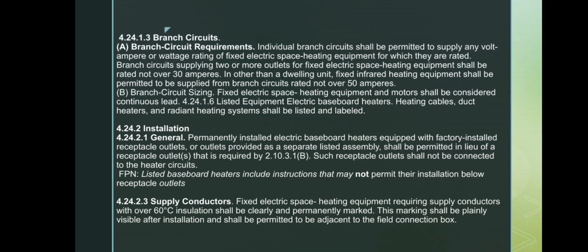The next slide explains the rules of branch circuit and installation for fixed electric space heating equipment. First, under section 4.24.1.3, branch circuit requirements. An individual branch circuit may supply any wattage or volt-ampere rating of fixed electric heaters as long as the circuit is properly rated. If one branch circuit feeds two or more heating outlets, it must not exceed 30 amperes. But in non-dwelling areas, infrared heaters may use branch circuits up to 50 amperes.